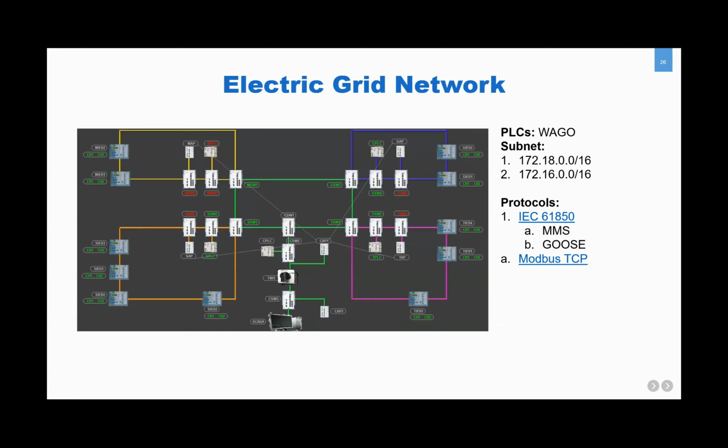So the protocols here you can expect will be the IEC 61850 standard, which is using MMS. MMS is the communication between the SCADA and the PLCs and IEDs, while GOOSE is the communication between IEDs. Yeah. We also have Modbus TCP. Modbus TCP is from the PLC to the VSD that controls the motor. Yeah. And here the PLCs we're using are the WAGO PLCs.